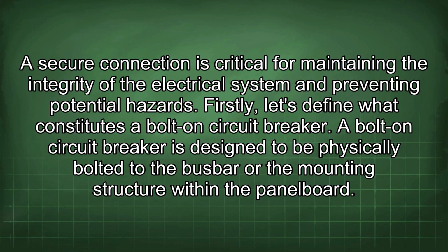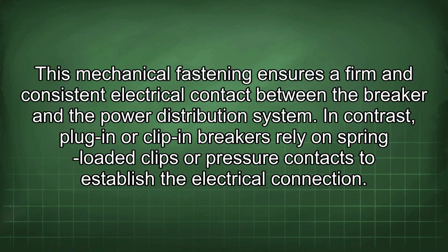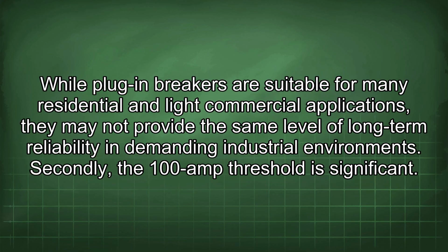Firstly, let's define what constitutes a bolt-on circuit breaker. A bolt-on circuit breaker is designed to be physically bolted to the busbar or the mounting structure within the panel board. This mechanical fastening ensures a firm and consistent electrical contact between the breaker and the power distribution system. In contrast, plug-in or clip-in breakers rely on spring-loaded clips or pressure contacts to establish the electrical connection. While plug-in breakers are suitable for many residential and light commercial applications, they may not provide the same level of long-term reliability in demanding industrial environments.